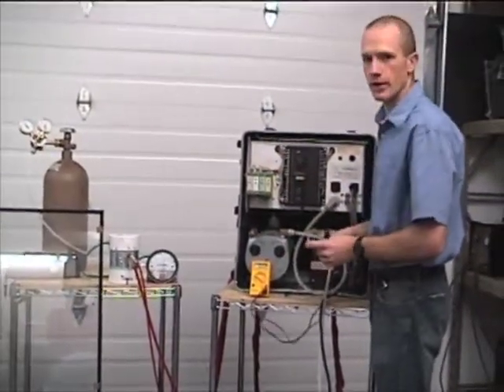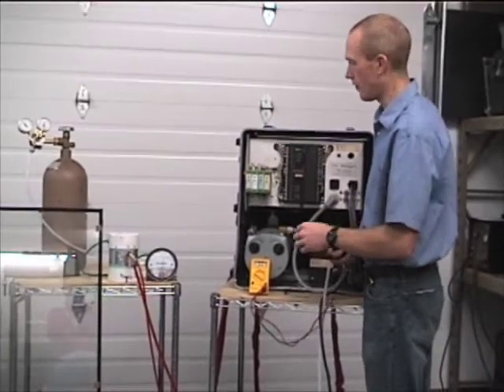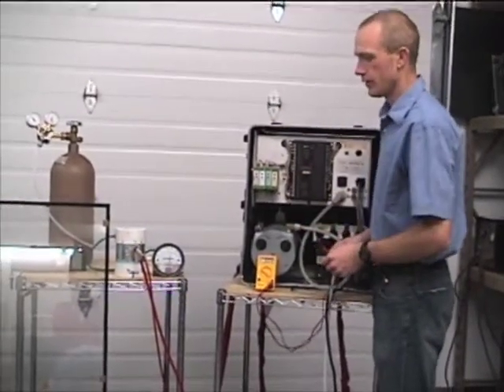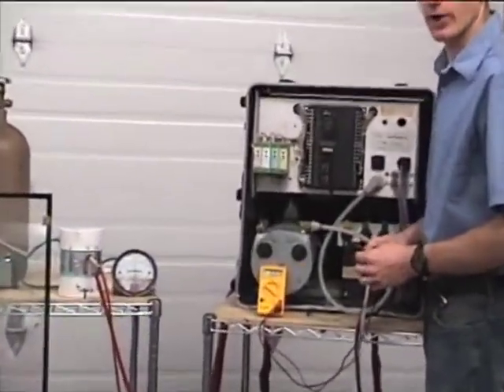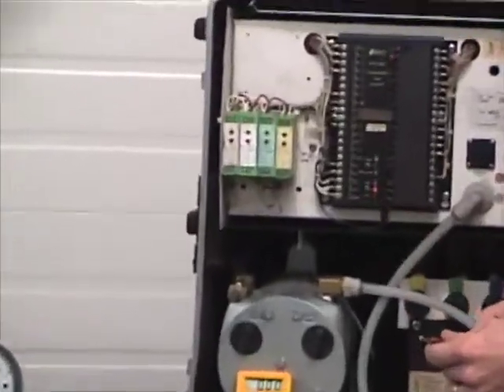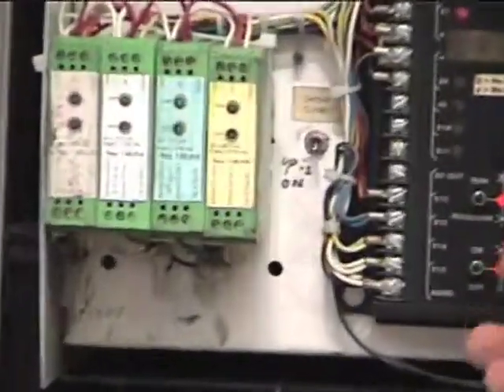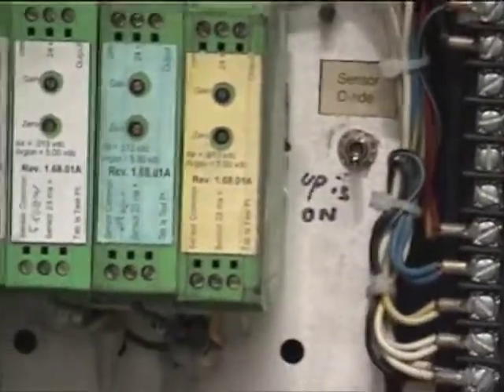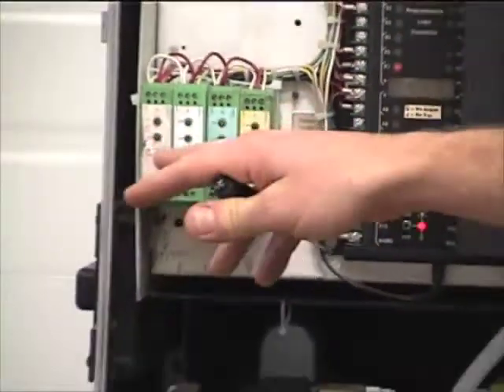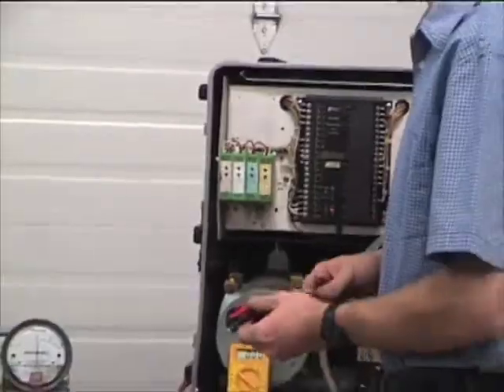When all that's been done, I can verify that the machine will shut off by itself by putting the sensor override switch down, and you can hear the machine is beeping. The end of the cycle has been completed and the machine is now ready to use, or that line is. So you'll have to go through the calibration for each line.